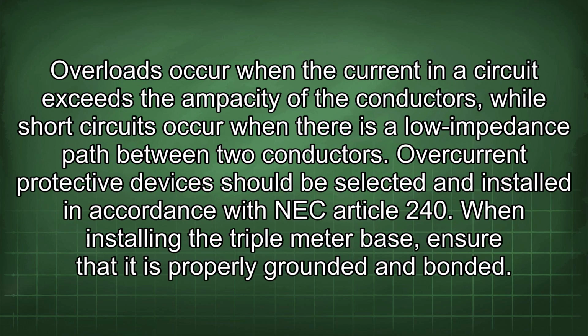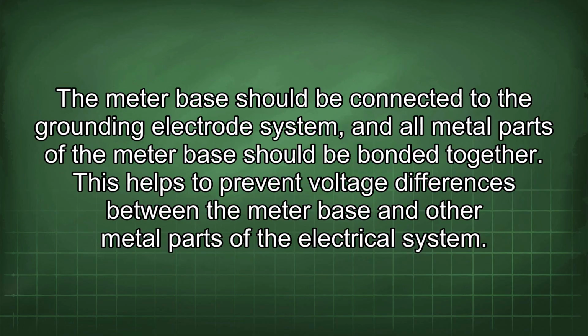Overloads occur when the current in a circuit exceeds the ampacity of the conductors, while short circuits occur when there is a low impedance path between two conductors. Overcurrent protective devices should be selected and installed in accordance with NEC Article 240. When installing the triple meter base, ensure that it is properly grounded and bonded. The meter base should be connected to the grounding electrode system, and all metal parts of the meter base should be bonded together. This helps to prevent voltage differences between the meter base and other metal parts of the electrical system.